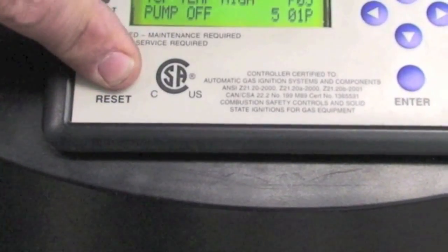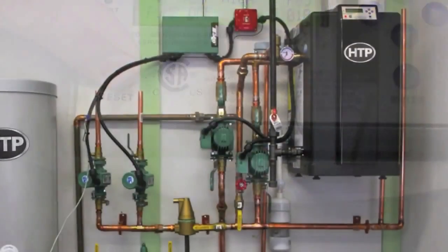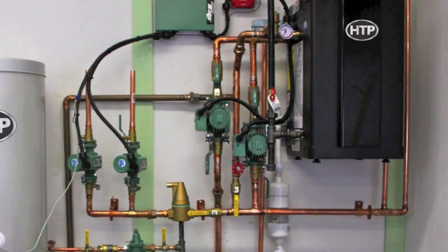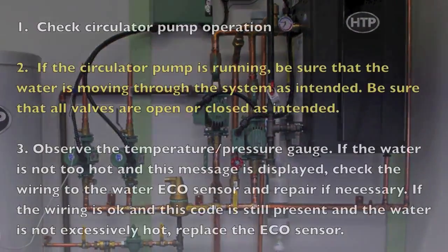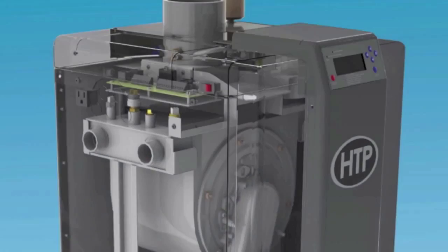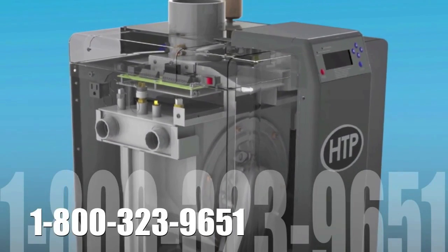Second, if you press the reset key and the heater operates, monitor the operation of the boiler and make sure the circulation pumps and zone valves are operating correctly and the boiler is getting proper flow. If the boiler circulating pumps or zone valves are bad, replace and put the boiler back in operation.